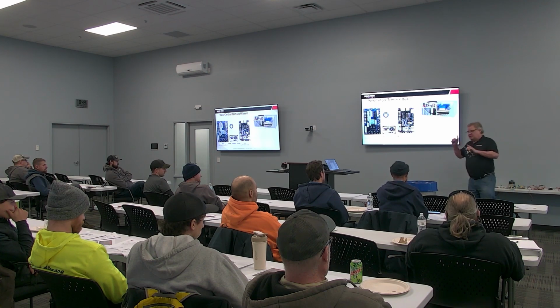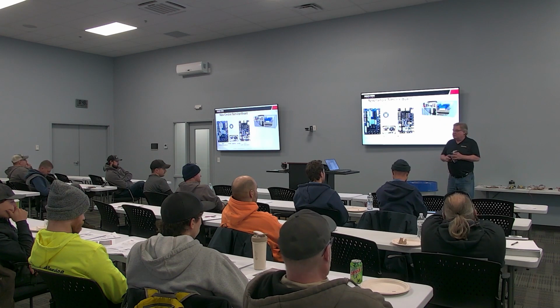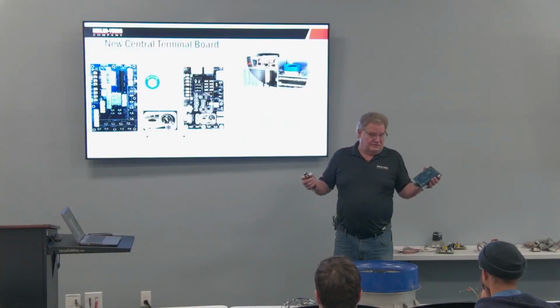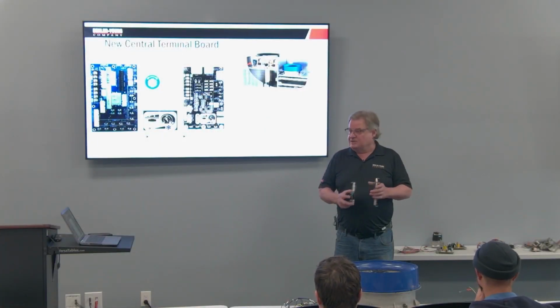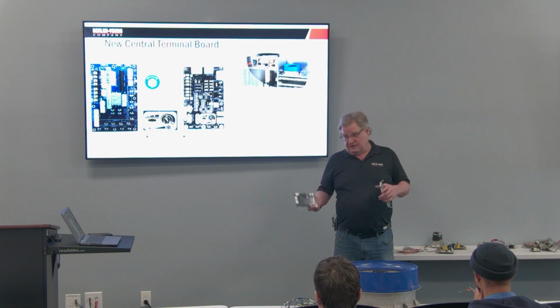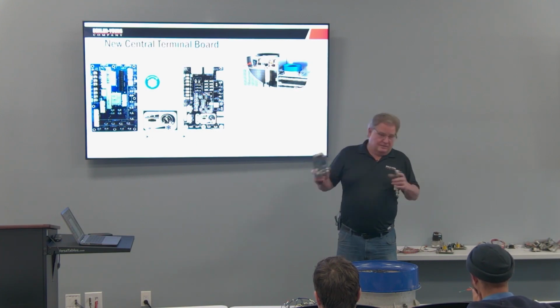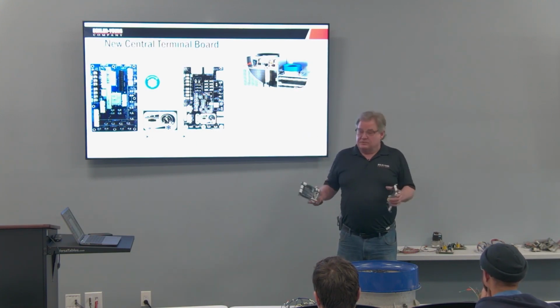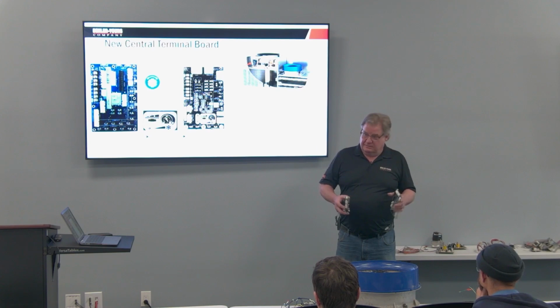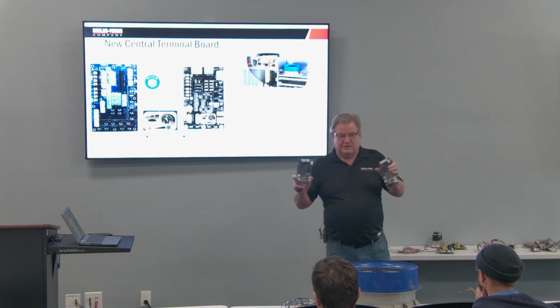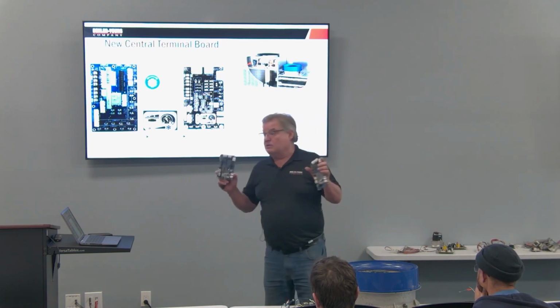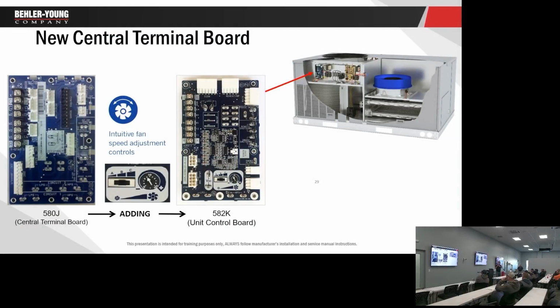Number one, they don't know what the static in your duct system is. And for those who don't know much about static, we're going to talk about that a little bit later on. But static's a really important thing. We don't know if we've got bad ductwork or good ductwork, so they don't know. Not to mention that unit's traveled over 2,000 miles before it got here. The old belt drive units, you have to adjust them. You've always had to adjust them. This we also have to adjust, and if we don't, one of the reasons we're going to get motor failures is not properly adjusting these. We're going to talk about that in a second.